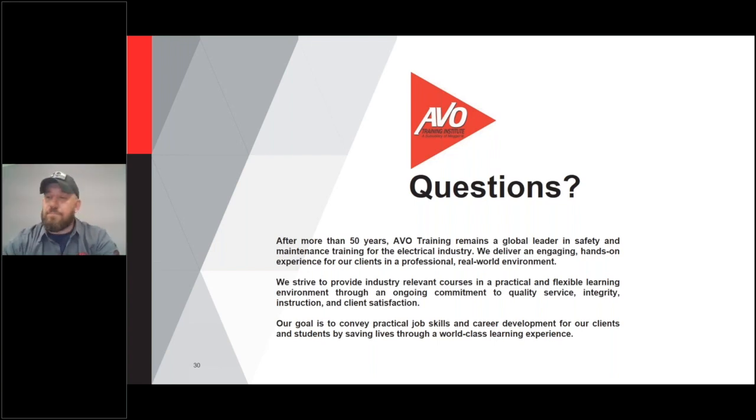Okay. Dennis has a question about one of the videos. It says the video did not show current swirling. Doesn't the arc swirl so we do not superheat the area of the contact? All right, so that's just an animation. That's all that is, just an animation to kind of show what goes on with the movable and fixed contact. And I like to pause that halfway through to show some key points. So you're right. I'm not going to say that it swirls, I'm not going to say that it dissipates equally inside the bottle, but the current generated will determine how those metallic ions act.